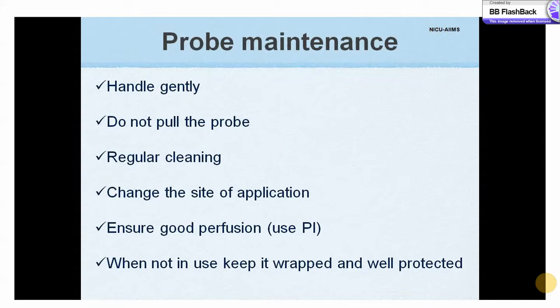Maintenance of a probe is as important as good fixation. Handle it gently and never pull the probe from the monitoring site. Regular cleaning will prevent cross infection. The site of application should be changed often, and before fixation ensure good perfusion with the aid of the perfusion index if available. When not in use, keep it wrapped and well protected from light, dust, and mechanical damage.